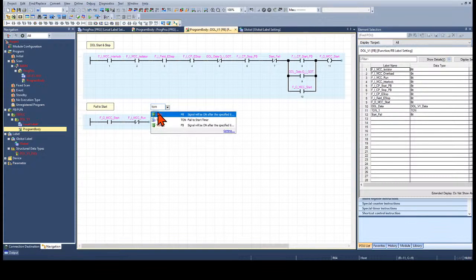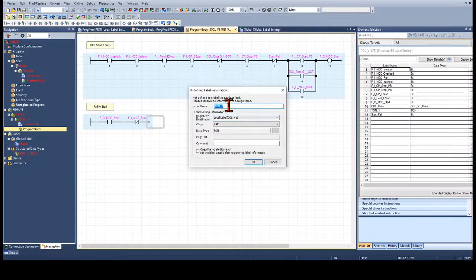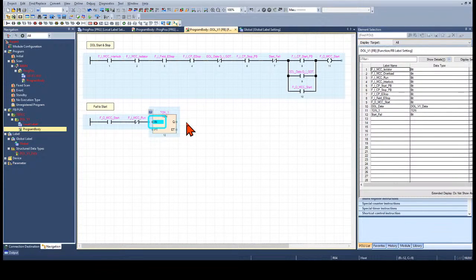a delay on timer. Just change that to 1 because I've already created a label, and that must switch output for us for that contact that we've placed there. So that will be our start fail contact. I'm just going to link that there, and then we're going to give it a time, how long it must take to time out before the contactor must fall out again. So that will be a T hash, and we're going to make it 2 seconds.